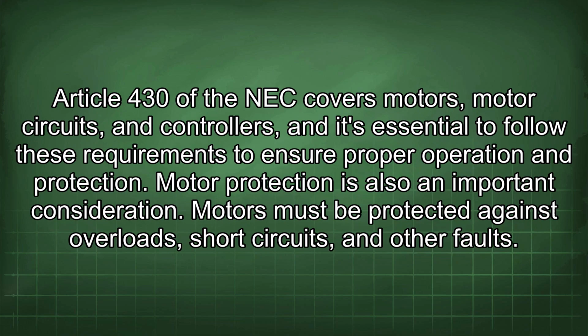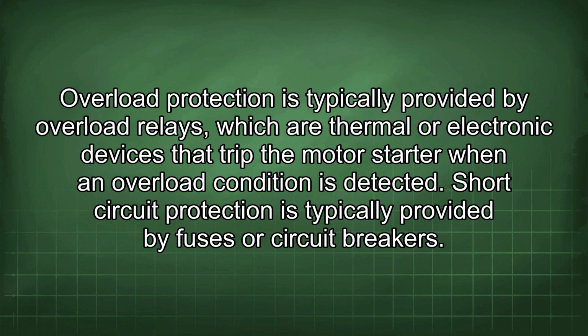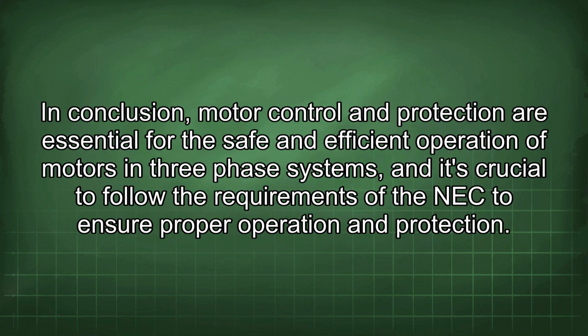Article 430 of the NEC covers motors, motor circuits, and controllers, and it's essential to follow these requirements to ensure proper operation and protection. Motor protection is also an important consideration. Motors must be protected against overloads, short circuits, and other faults. Overload protection is typically provided by overload relays, which are thermal or electronic devices that trip the motor starter when an overload condition is detected. Short circuit protection is typically provided by fuses or circuit breakers. In conclusion, motor control and protection are essential for the safe and efficient operation of motors in three-phase systems, and it's crucial to follow the requirements of the NEC to ensure proper operation and protection.